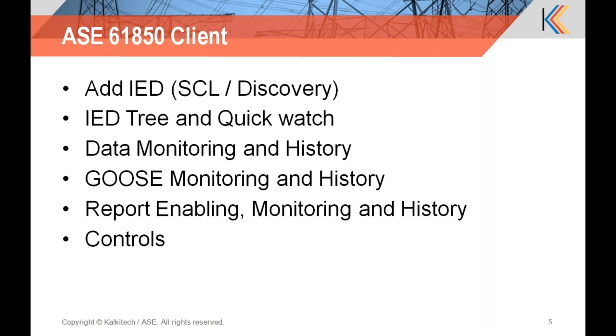On the client side, we will have the add IED feature. We will have the IEDs loaded into the client system through a SCL file. We will browse the IED tree and also see the quick watch feature so that you can view the data points very easily. Further, we will see the data monitoring functionality and history of those data points. We will also extend our demo to GOOSE monitoring and history, further to report enabling, monitoring and history, and finally the controls. Time is short, we will have to go a bit faster, but I will try to cover all these aspects.